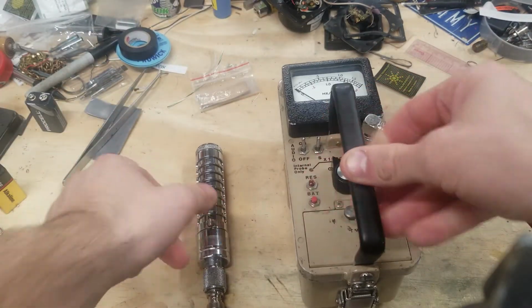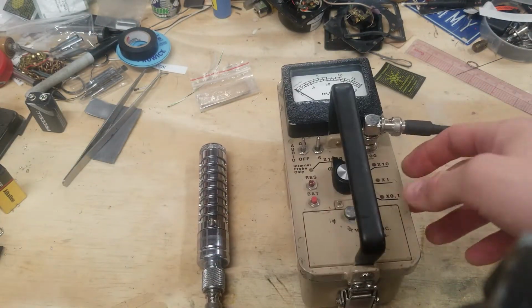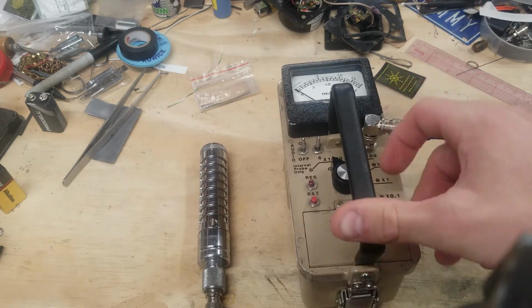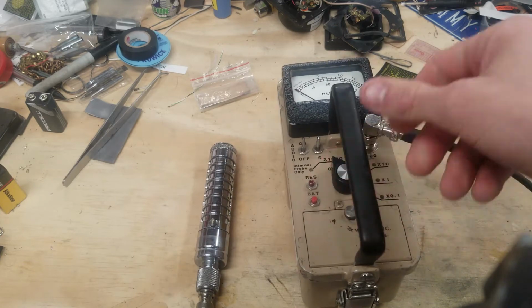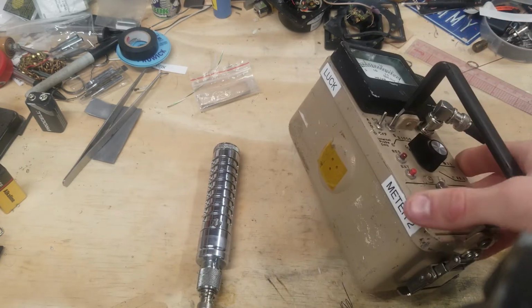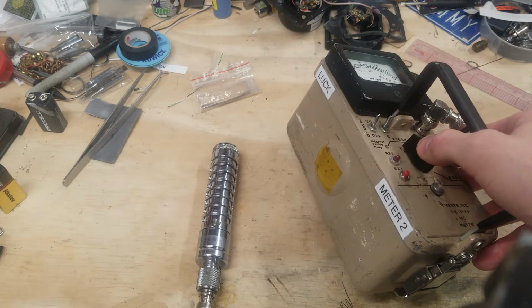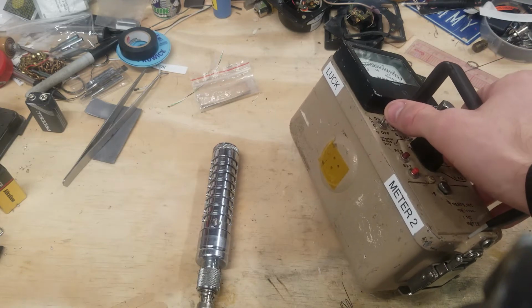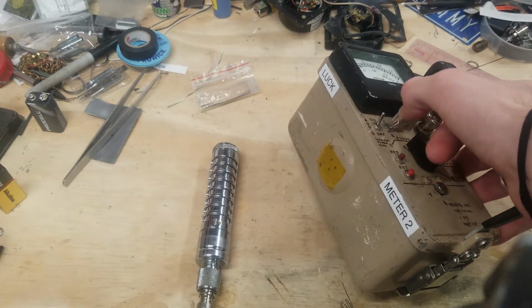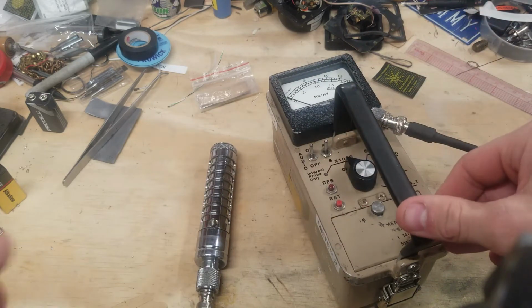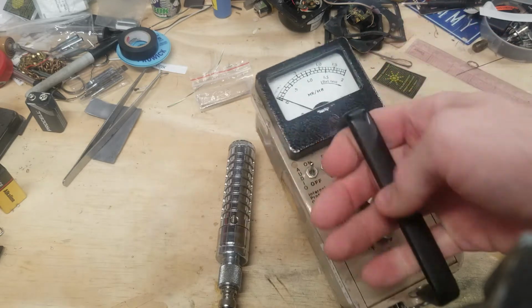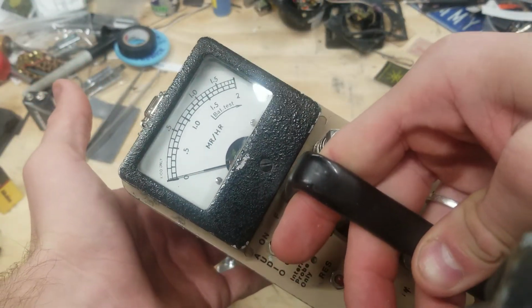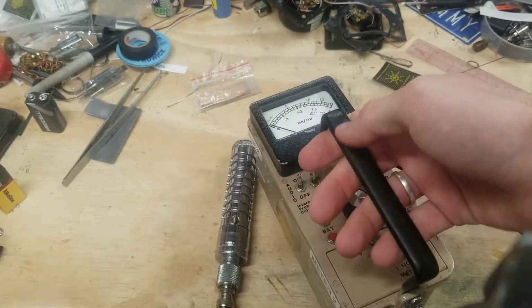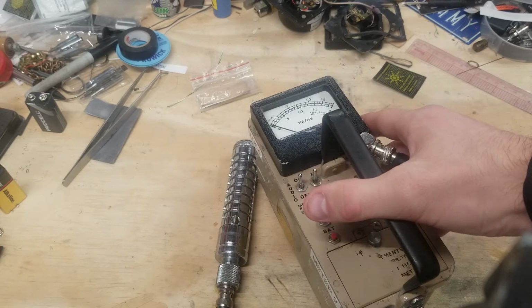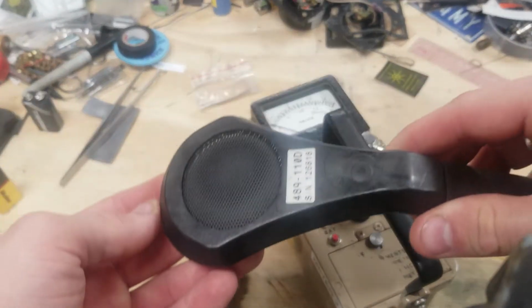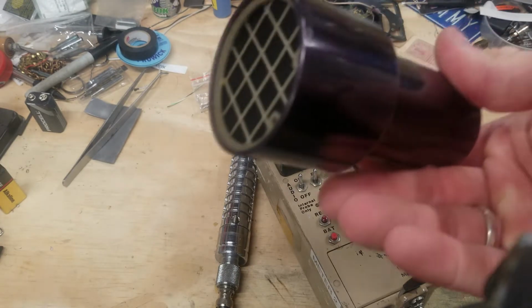The Ludlum Measurements Model 14C is a multi-use survey meter that incorporates an external probe and an internal probe. Just like its predecessors, it incorporates a reset button, a bat test, a multi-position rotary switch, an audio on-off with an external speaker, and a fast and slow response switch to control the needle movement. In this case, this meter was designed for dosage only, as seen by the scale. Not all of them are designed for dosage only, and many of them have a counts per minute scale to be used with a pancake or an end window type detector.